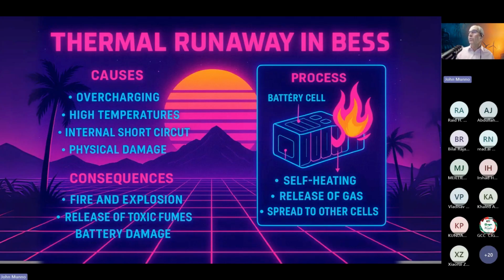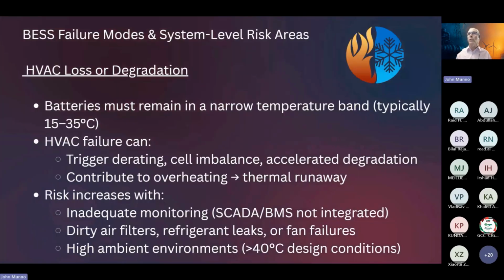With that, they also say they don't need a fire suppression system because they're not going to have a fire. They may have thermal runaway, but they're going to deal with the gases before they become too great and could cause an explosion that destroys the modules. What else can go wrong?